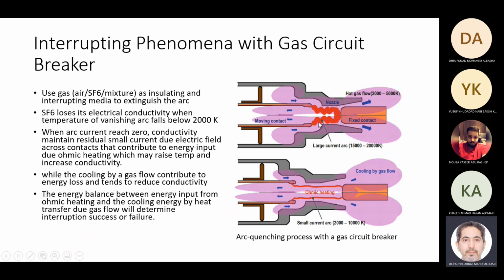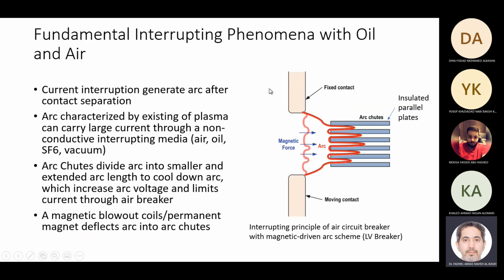So what it does is cool this heat. There will be heat generated from the arc as a result of I squared R, and there is also cooling from the gas. When the cooling energy is more than the heating energy, this arc will be extinguished. This is the second principle, the energy balance theory.